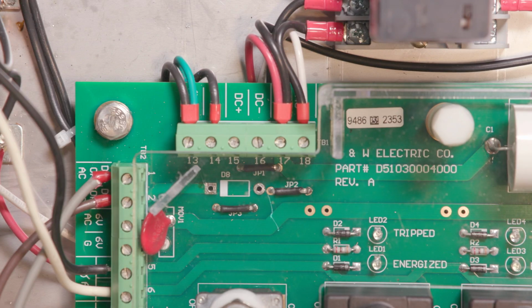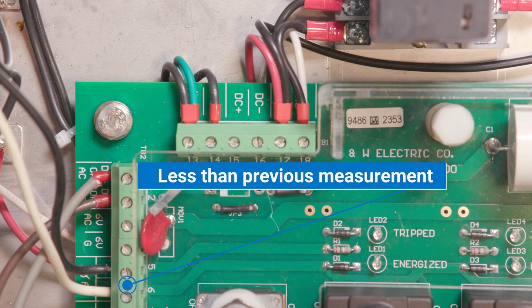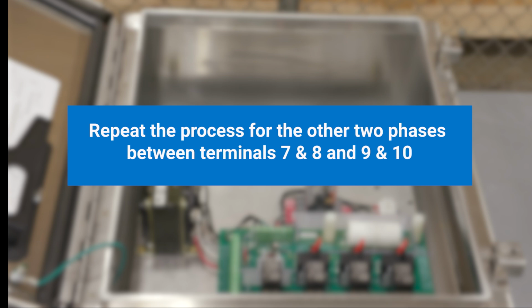Measure and record the AC output of the step-down transformer across terminals 13 and 14 on the circuit board. Voltage should be 6.5 to 8 VAC. Record the output voltages to the ITs at terminals 5 and 6. The voltages should be slightly less than the previous measurement. Repeat the process for the other two phases between terminals 7 and 8 and between 9 and 10.